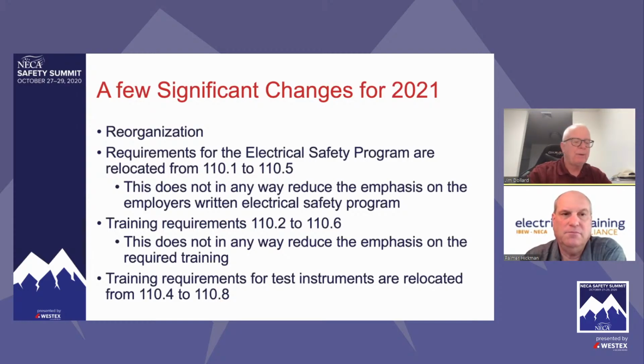Yeah, and Palmer and I, we have done 70E training for journeyman wiremen, and the contractors are in the room, and we have to tell them, look, when we're done with this training, you're not done, because we're not training you on the test instrument that you're going to use. So the employer, that's you, have to identify what test instruments they're going to use. So if the test instruments are only for measuring voltage, then the easiest thing to do is buy one type of test instrument. If it's only being used to verify the absence of voltage, it could be a solenoid type test instrument that's a voltage detector, and you train everybody on the same one, and you got it done.